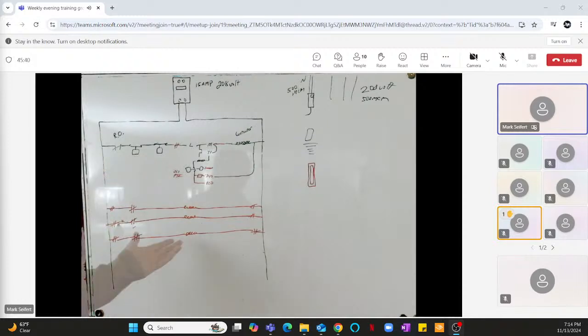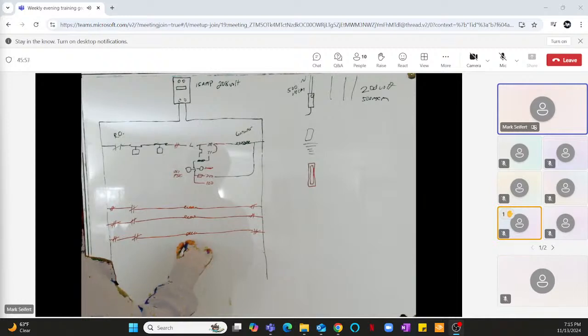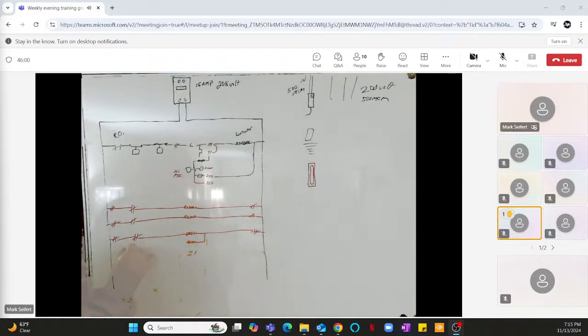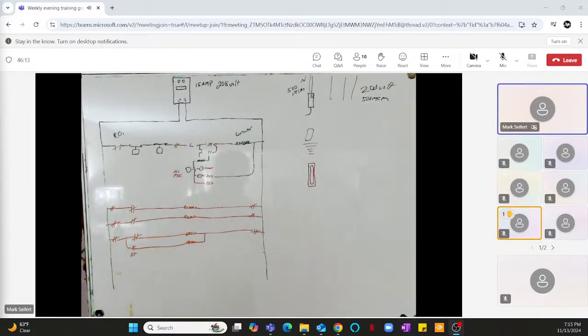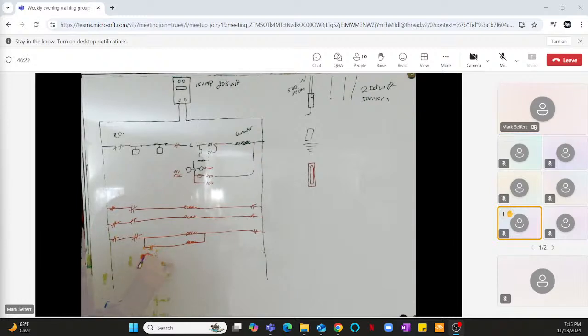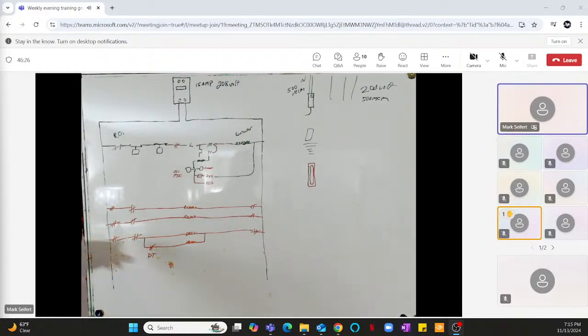Yeah, there's going to be some stuff where there's some dual temp, but that's going to be nothing more than, at the rack, you're going to have a different RO that's going to give it another dual temp, or a toggle switch. Let's just call it a toggle switch here for dual temp. A bypass solenoid. Actually, it'll come from here. My bad. Come from here. Dual temp. But it just adds. You just add it in there.